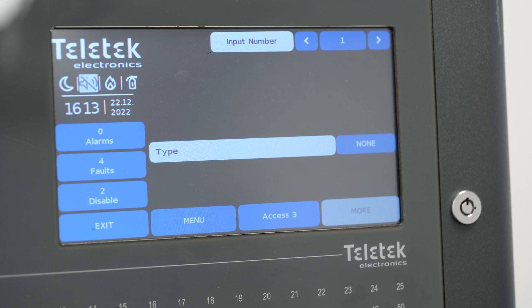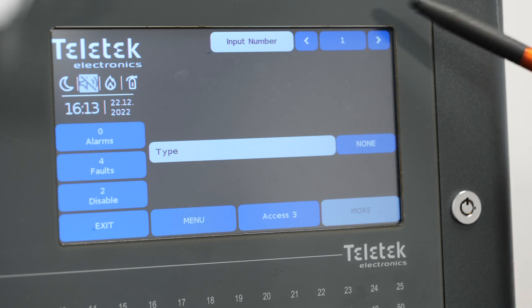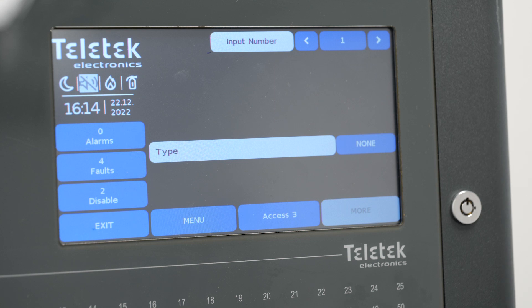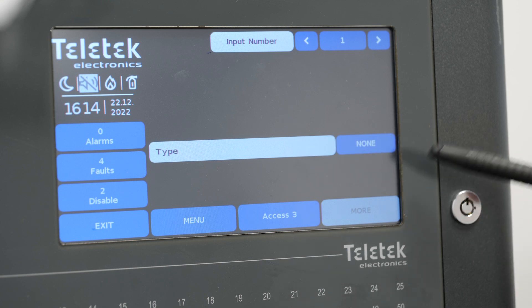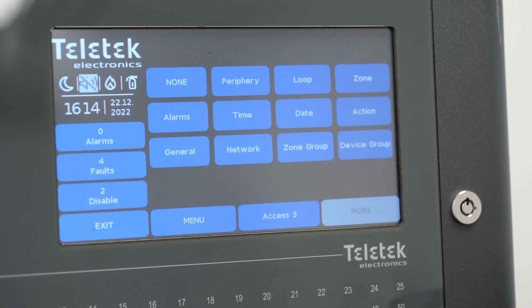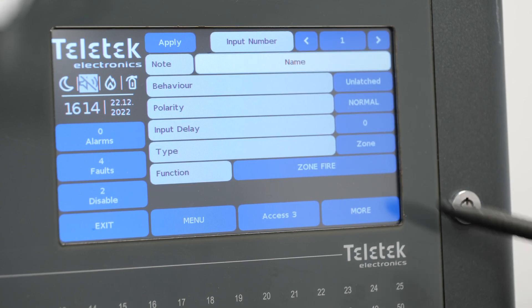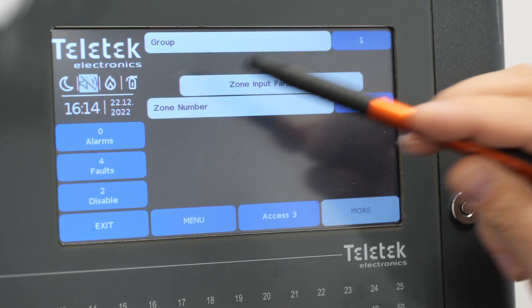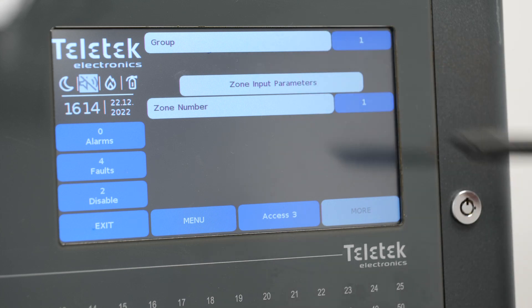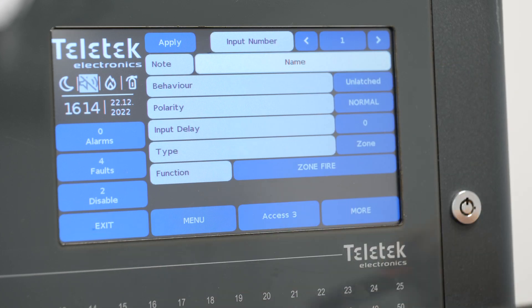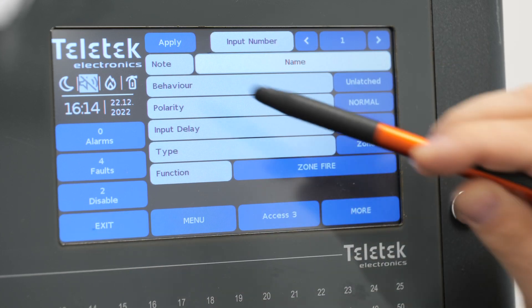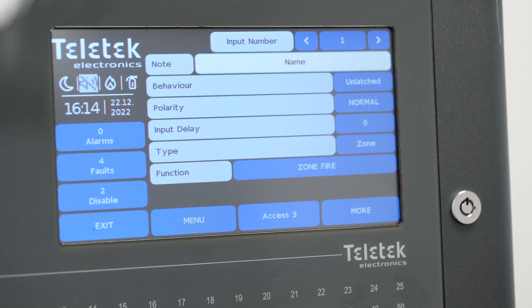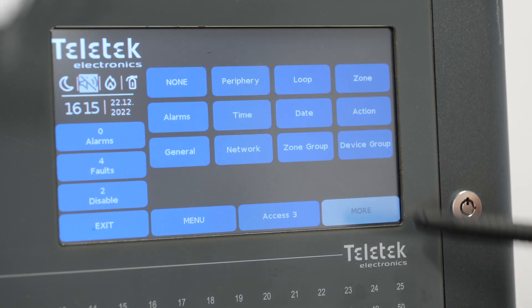The first one we are going to create is input number 1 which will be linked with the event of fire in zone 1. Type none means this input hasn't been used until now so it is free for us to use. We choose type zone fire and zone number 1. After the correct settings are selected, press apply to save the changes and move on to the next input.